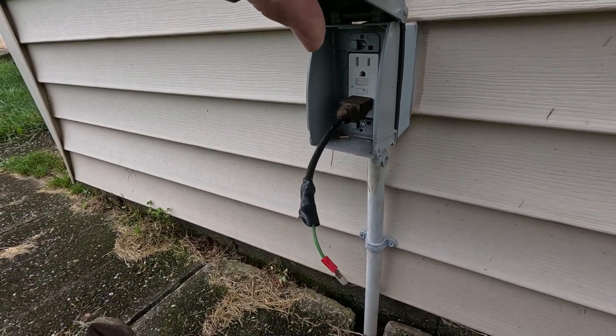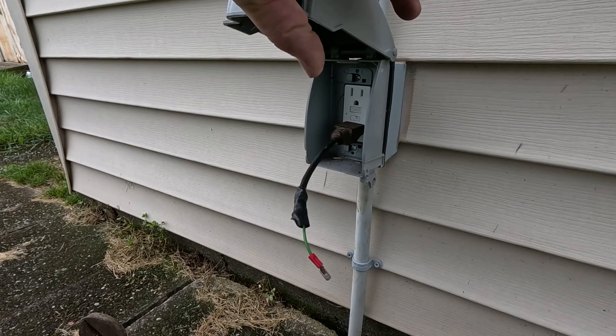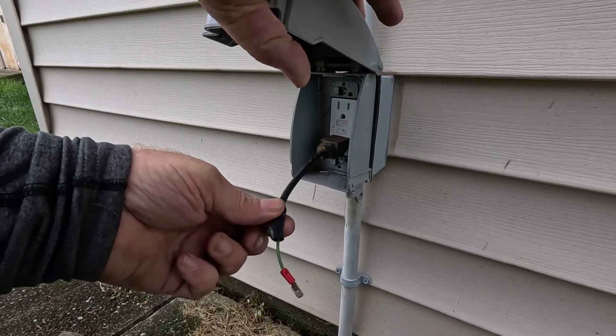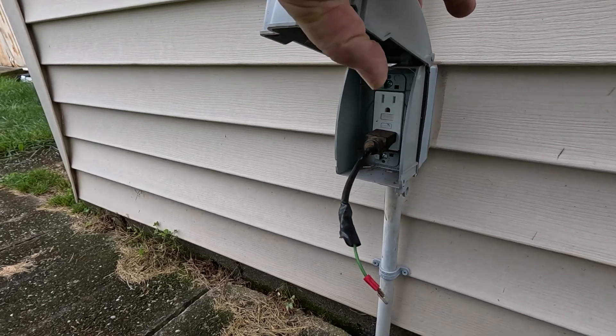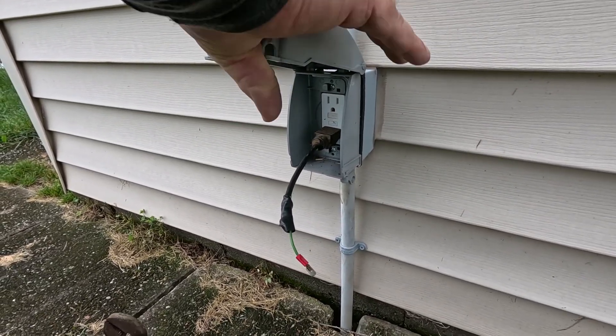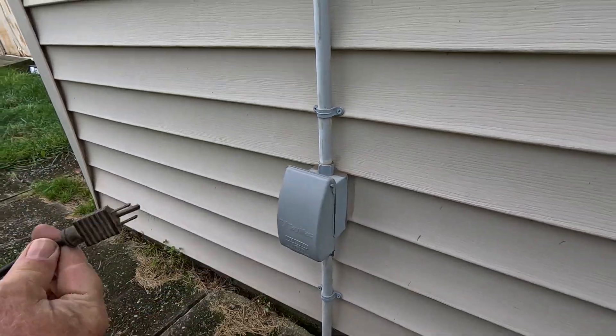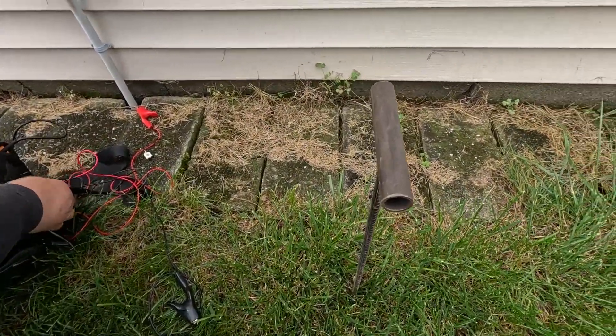That's how I check outlets — where there's a line going to the outlet, both the hot and the neutral are cut. This just goes to the ground, so I sent a signal down the ground wire and that's how I locate the wire with that little jumper. And here's the grounding rod right here.